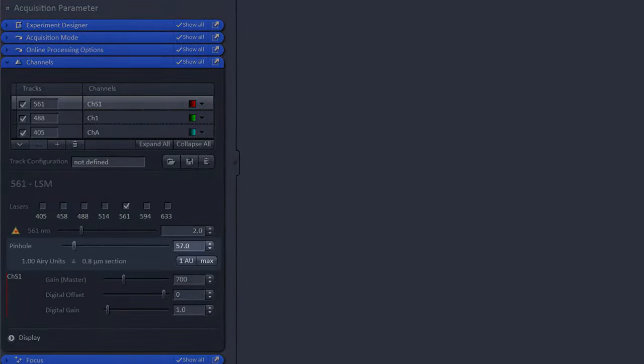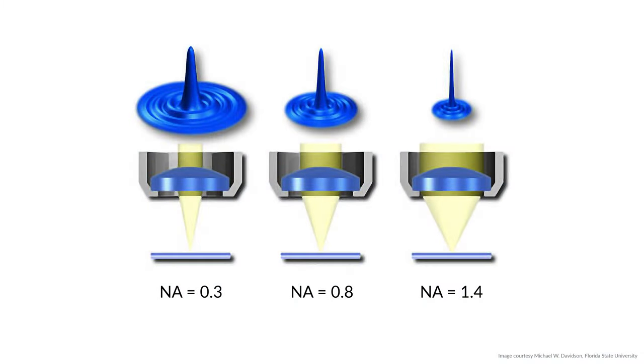The diameter of the pinhole is expressed in airy units on a confocal microscope. In the software control of a confocal, you will find your optical section thickness calculation accompanied by this airy unit calculation. Setting this value to one airy unit for your longest wavelength fluorophore is a common compromise value between the signal collected and the resolution of the system. In addition to the pinhole diameter, the numerical aperture, or NA, of the objective lens has the largest influence on overall resolution.